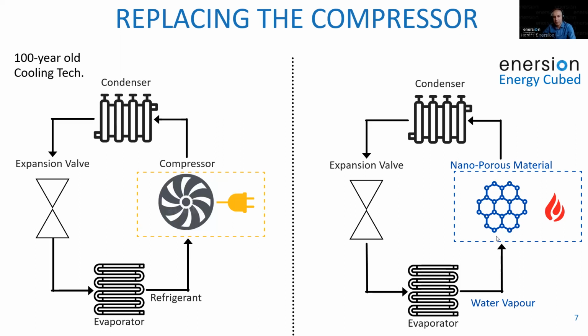Because of that surface area, in our evaporator we just put water - there's no synthesized refrigerant. The water sees the nanoporous material as a solid desiccant, a dry solid desiccant, so it starts rapidly evaporating into the surface of the powder. At some point the powder loses efficiency because it gets soaked with water vapor. At that point we close a valve and use hot water over a heat exchanger to dry the powder and push it to the condenser. Once that gets condensed, just like the traditional cycle, we kill the pressure and take it back to the evaporator. That's how the thermodynamic cycle works.